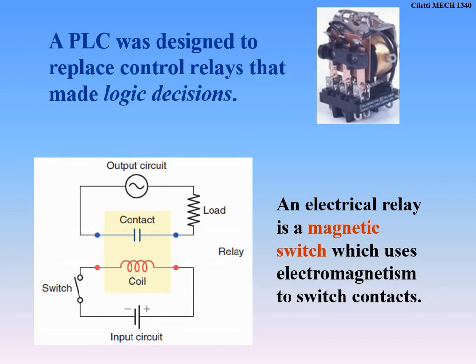As discussed in an earlier lecture, the whole purpose of a PLC is to replace control relays because of wiring and cost. The big advantage is we can make quick changes in a PLC ladder logic program without physically going out to the field to rewire, which could take hours in a messy cabinet. We still use relays to open and close, but we control them with a PLC rather than wiring relay to relay.